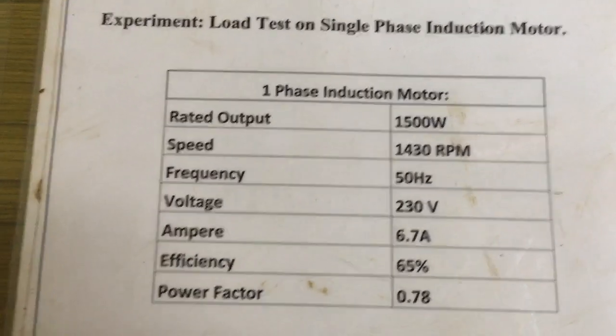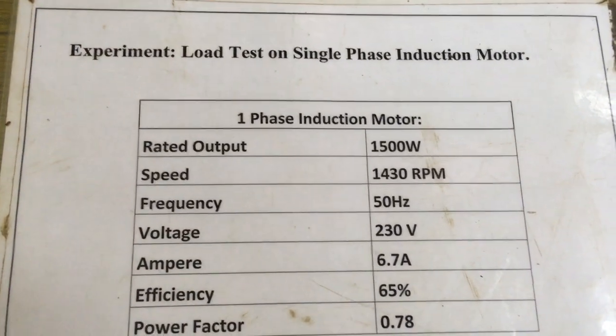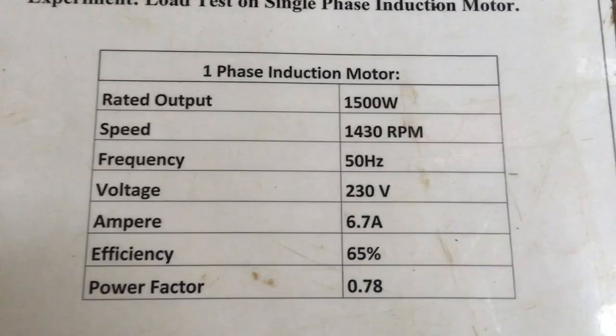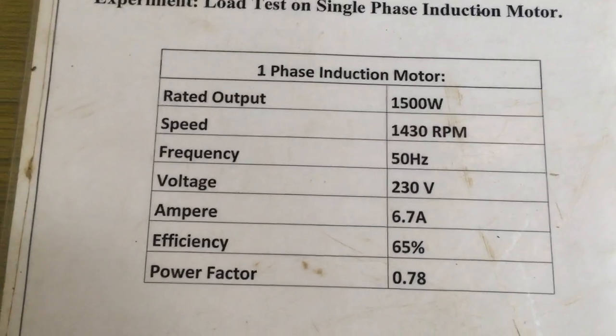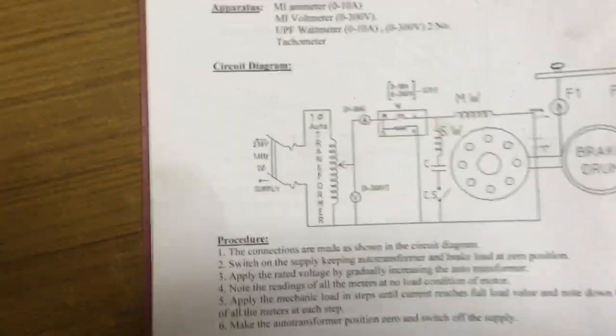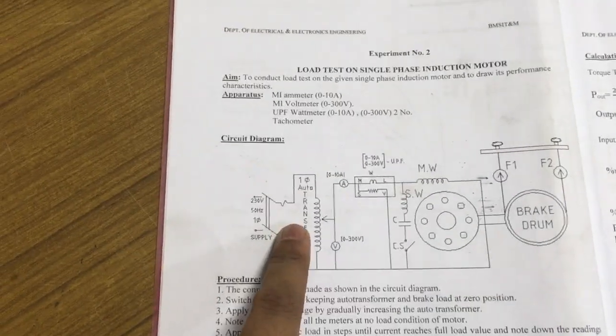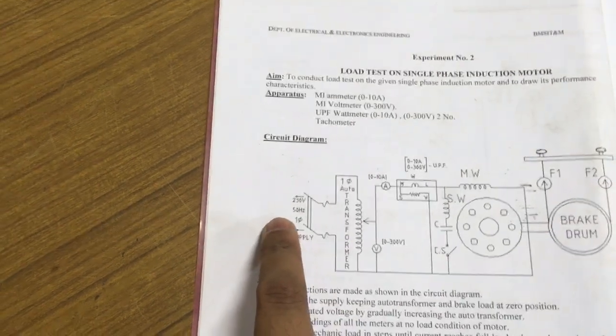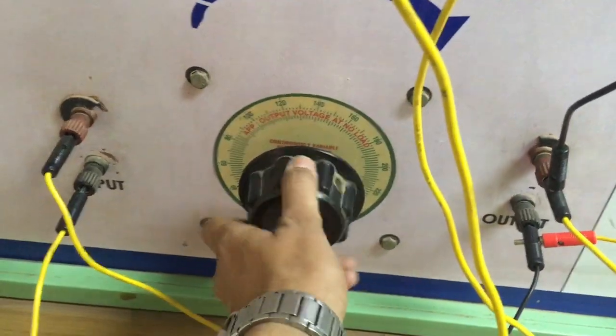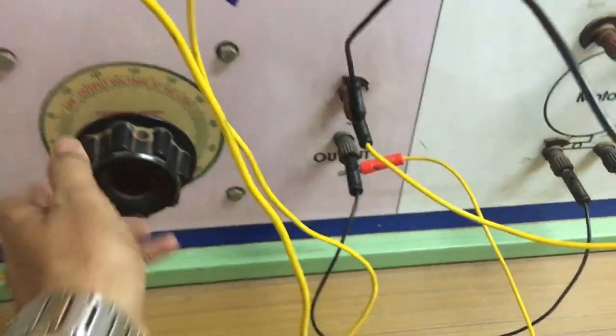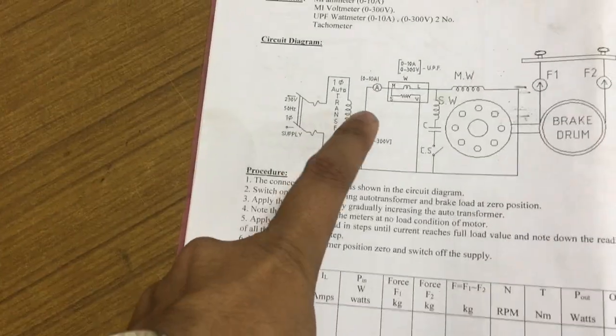The specifications of the motor are given in this sheet. It is a 1500 watt, 1430 rpm, 50 hertz, 230 volt, 6.7 ampere motor. So the full load current rating of the motor is 6.7 amperes. The circuit connections are as shown. We are starting the motor using an auto transformer starter. This is the single phase auto transformer that I use, connected to the supply switch. The auto transformer knob is provided here. The auto transformer winding is connected at the back of the panel board. So through the auto transformer I am starting the motor.